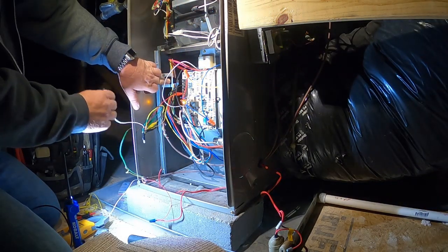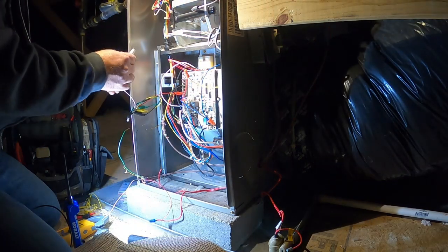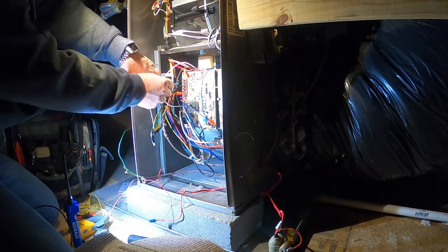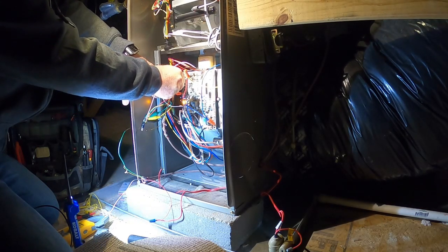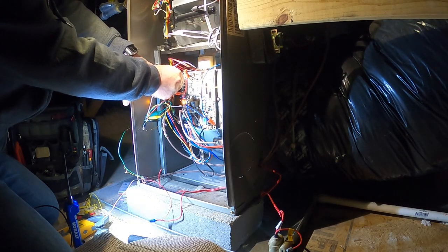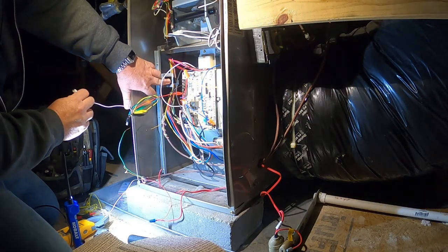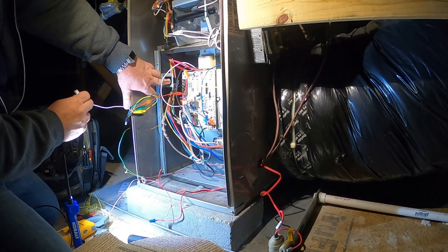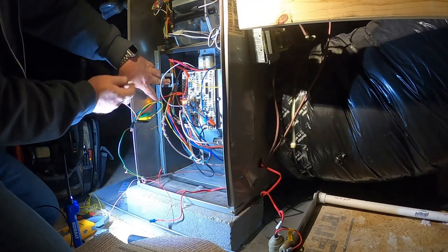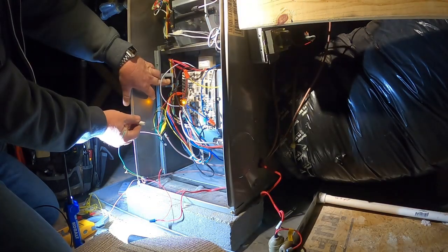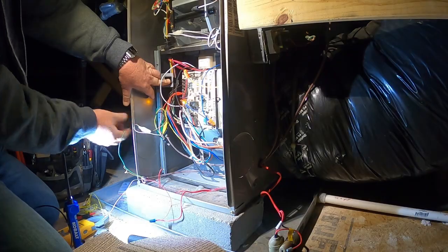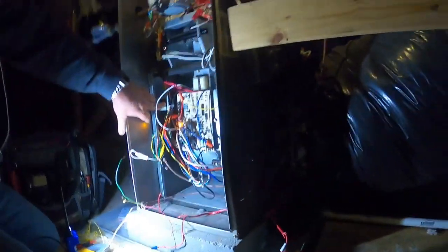Oh, duh. Those are the thermostat wires. Okay, R to G. So we have airflow. Now I'm going to jump R to Y going outside. See if the condenser comes on. Yeah. The outdoor unit is operational.